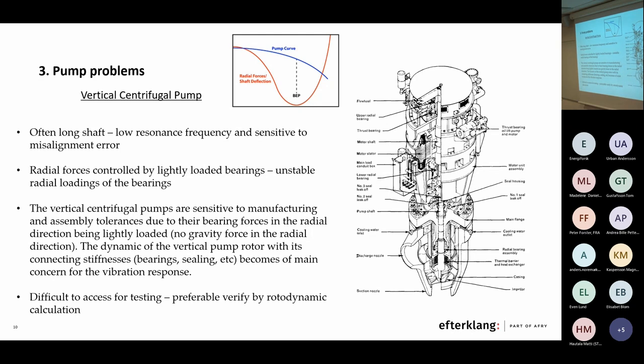And as you see on such a pump here, you cannot put the sensor so easily on this. You do not have much contact with the different shafts. Otherwise, you can set sensors on the top of it, etc., depending on what you are allowed to do, so to speak. So you get just a glimpse of what the vibration pattern really is inside this structure. So it's also beneficial that when you analyze a vibration problem for a vertical pump, you should always have, according to our experience at Efterklang, a rudimentary calculation with you.